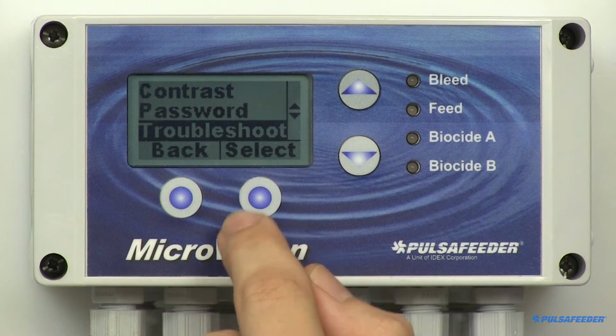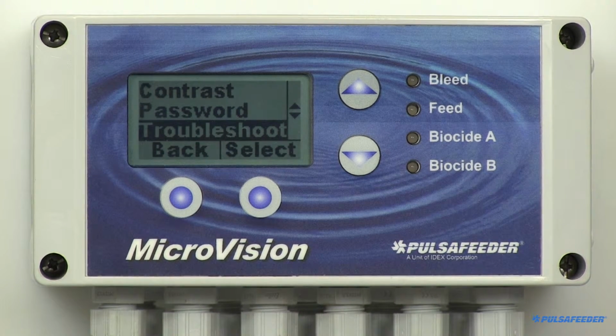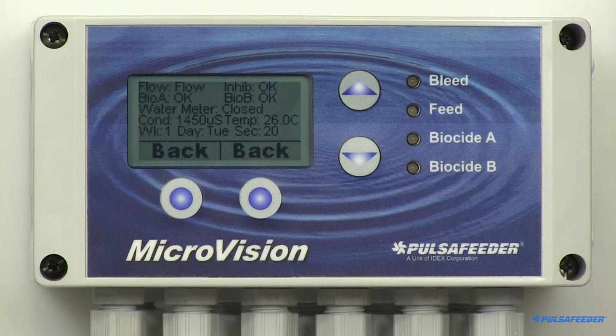A tool for checking the operation of the MicroVision in real time is the Troubleshoot screen. Find it by scrolling down and selecting it. Displayed is the flow switch status, the four drum level switch statuses, the water meter status, the probes, conductivity, and temperature reading. It also shows the revolving week number and the day of the week used in biocide programming. We'll cover that later. And lastly, the clock seconds. While the screen is displaying information, the controller is still functioning normally, and the relays could energize without warning.